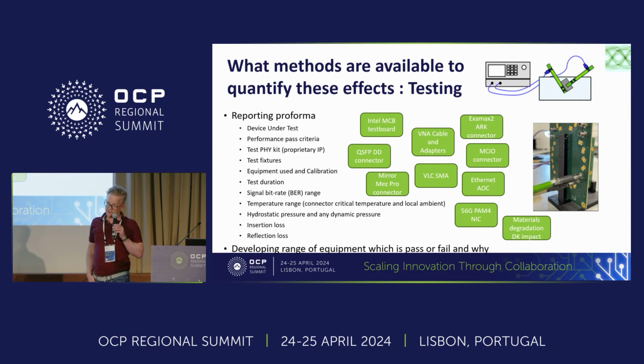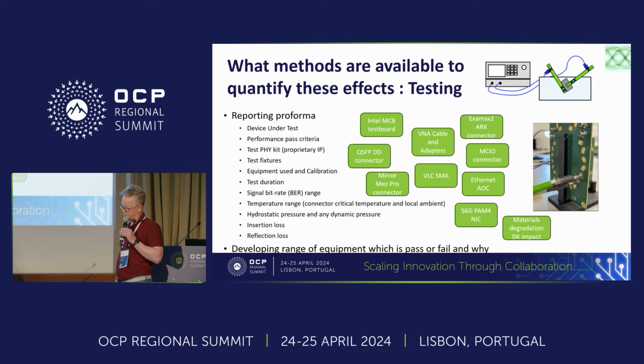So we can control the liquid by having a specification, and when we select a liquid for a certain purpose, we can use the base specification from OCP to increase our chances of success. When we get into immersion, though, you need to, of course, do a component-by-component test to understand if you have an issue, what you can do about it, where you're going to focus your attention.